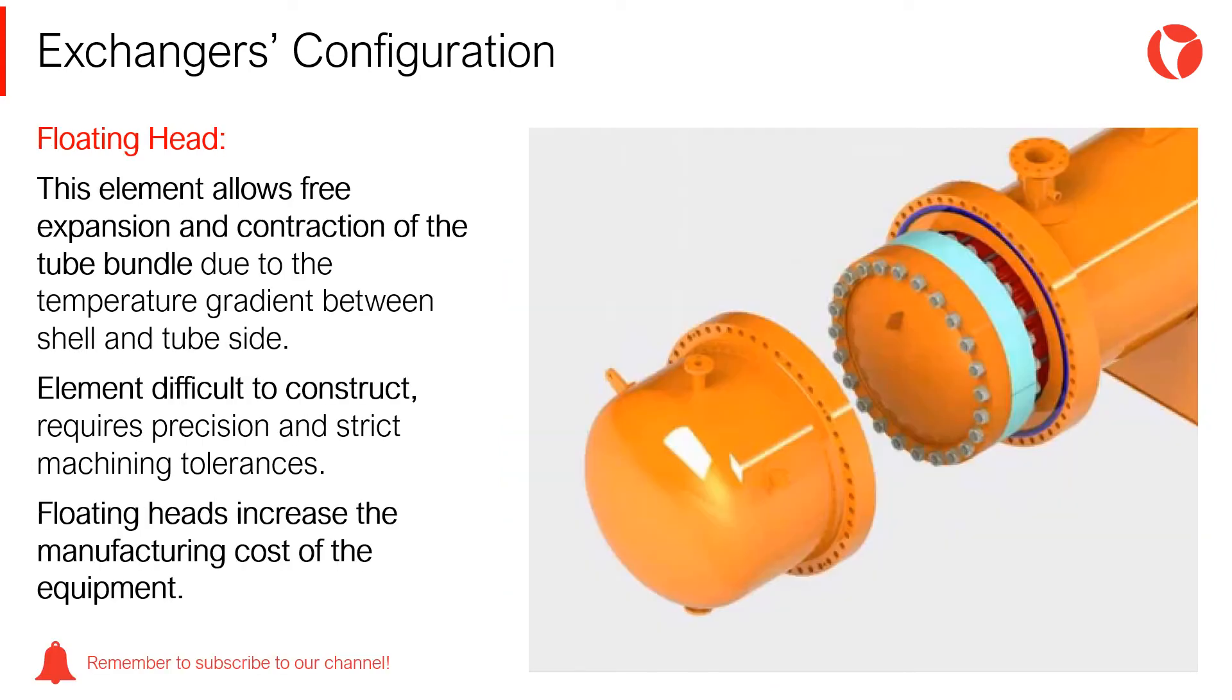And finally, the floating head. This element allows free expansion and contraction of the tube bundle due to the temperature gradient between the shell and the tube side. This element is difficult to construct, requires precision and strict machining tolerances. Floating head increases manufacturing cost of the equipment significantly.